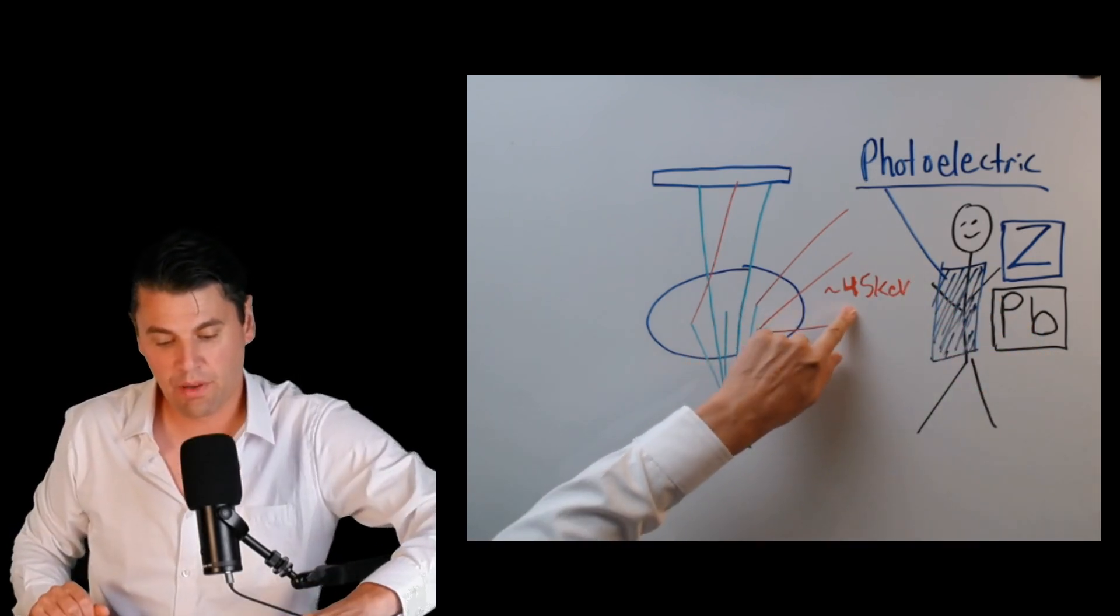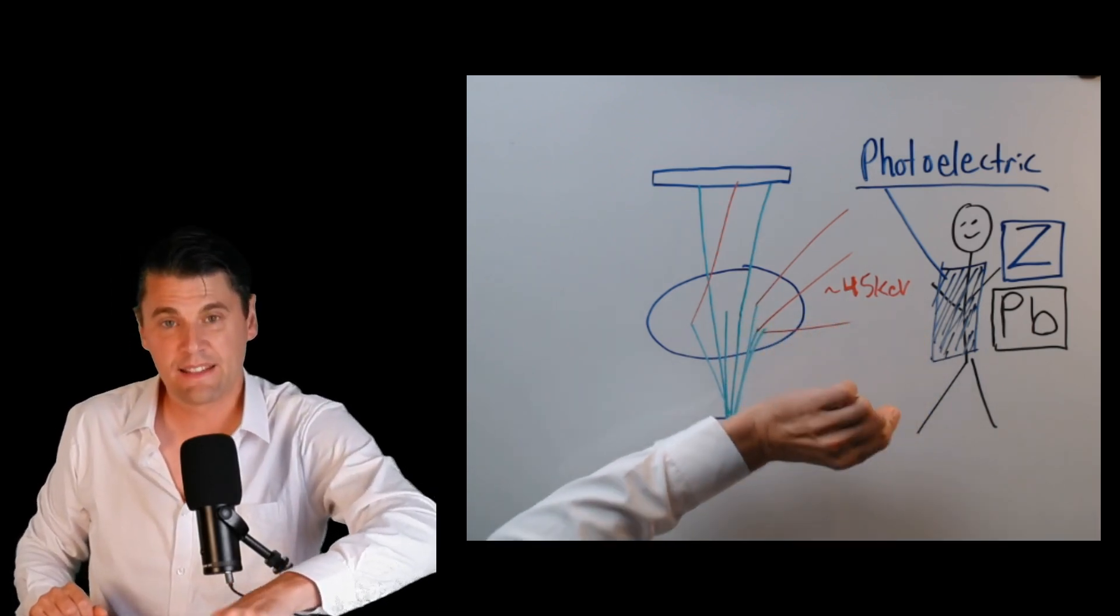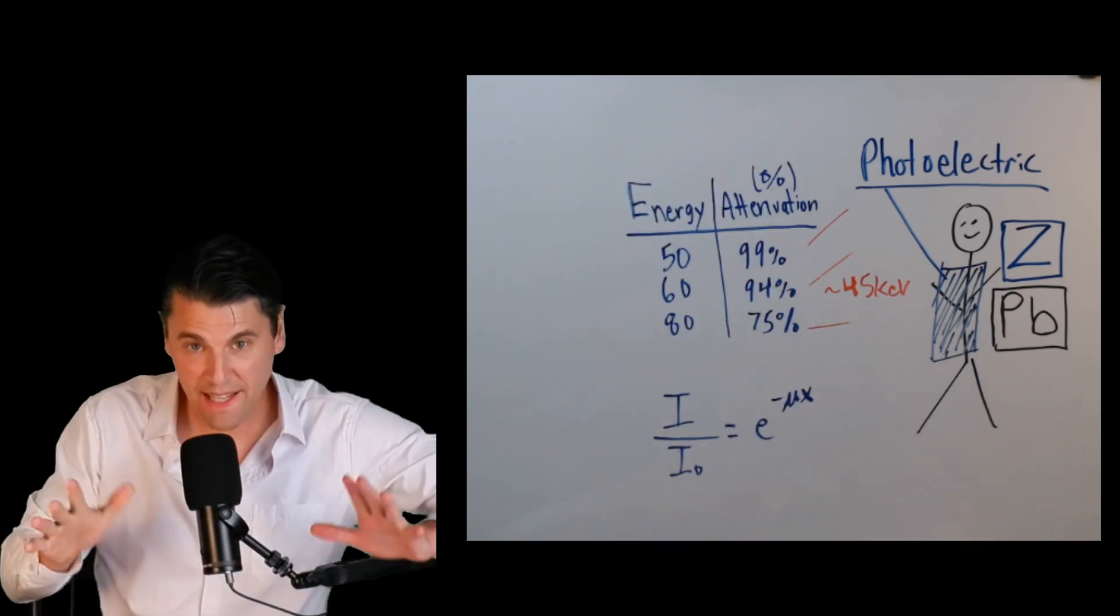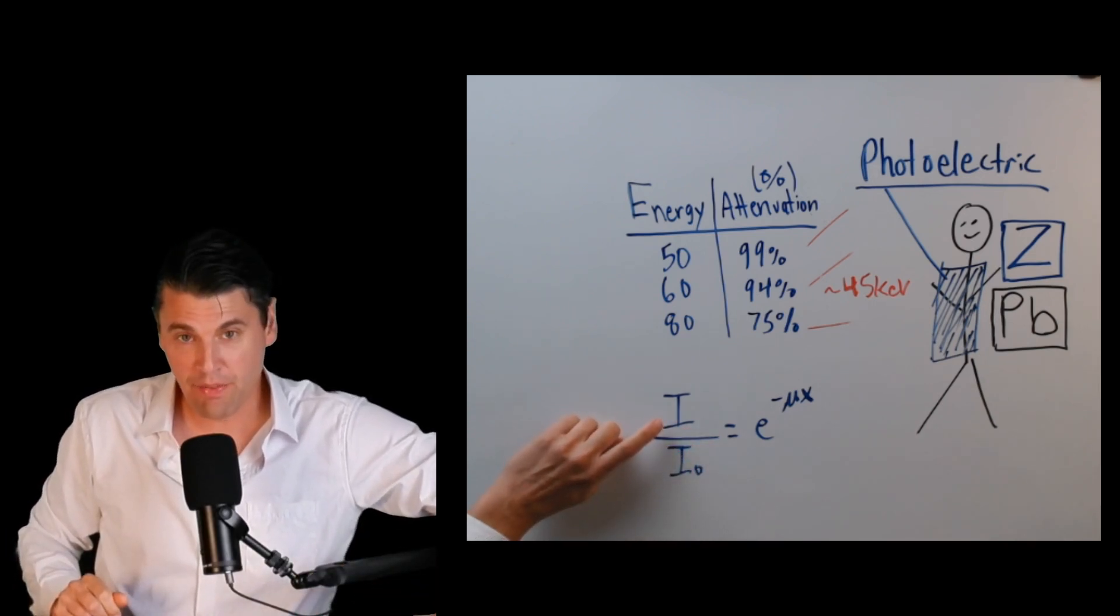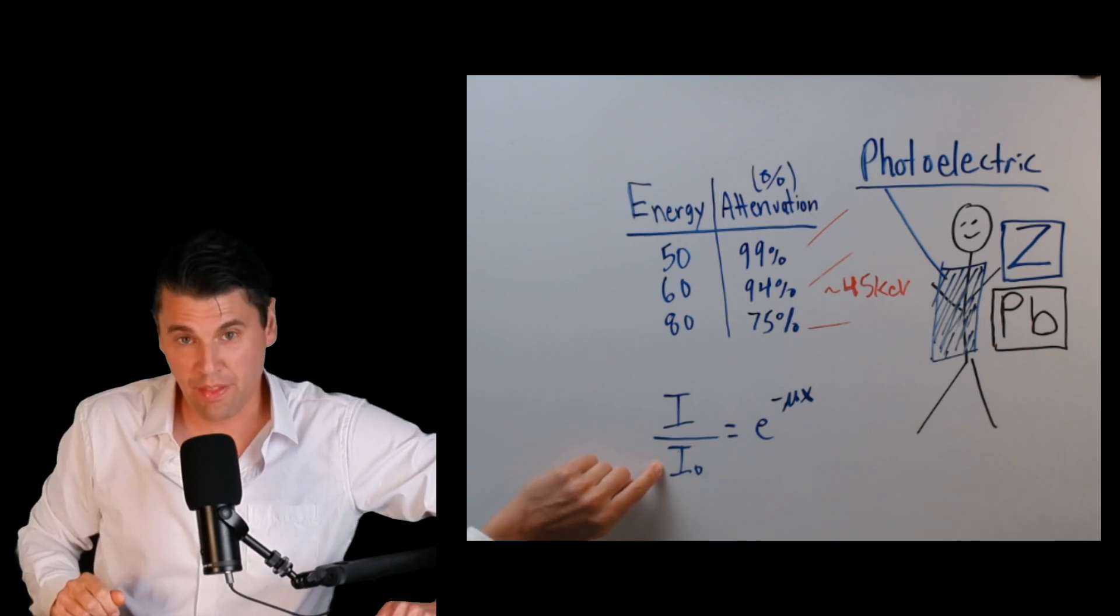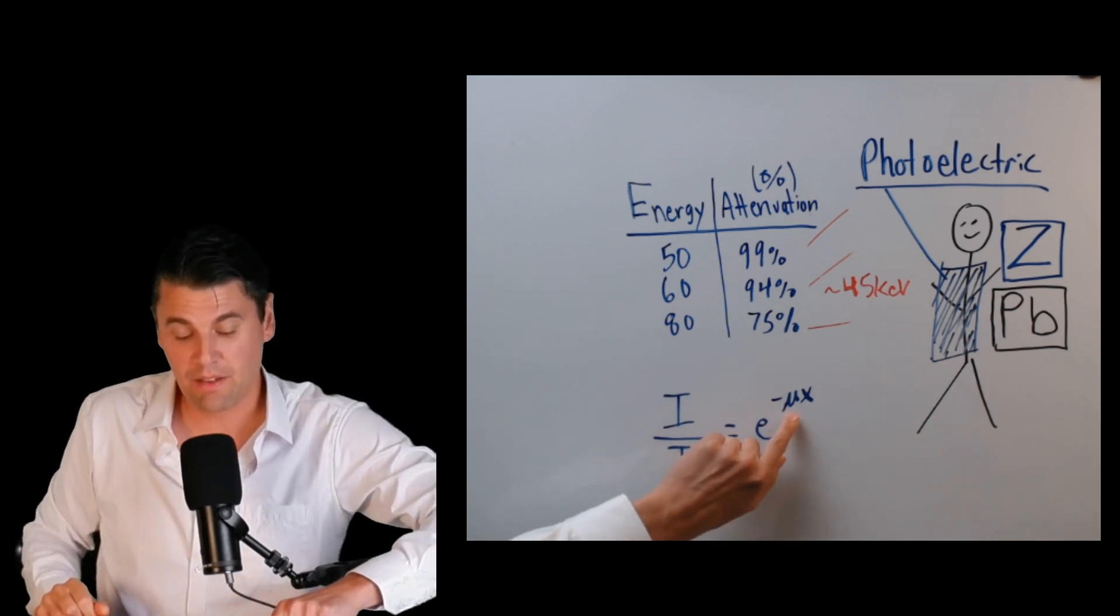We have x-ray photons that are in the mid 40s of the KEV on average, and we would like to stop them with a very high likelihood. We can use something called Beer's Law to actually calculate the amount of x-rays or the intensity of x-rays that are coming through compared with the x-rays which were initially incident on our shield. It's e to the minus mu x, where mu is what we call the linear attenuation coefficient.